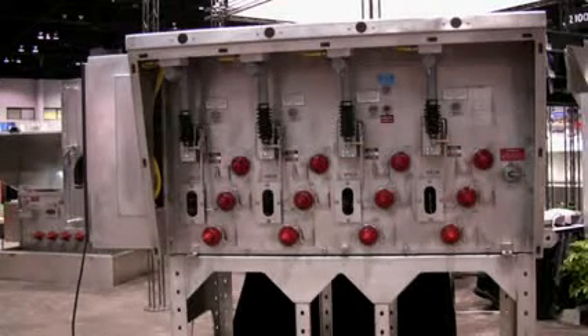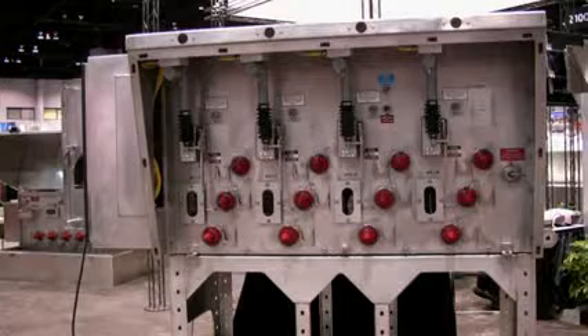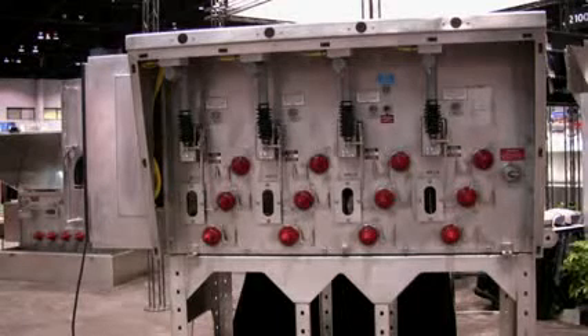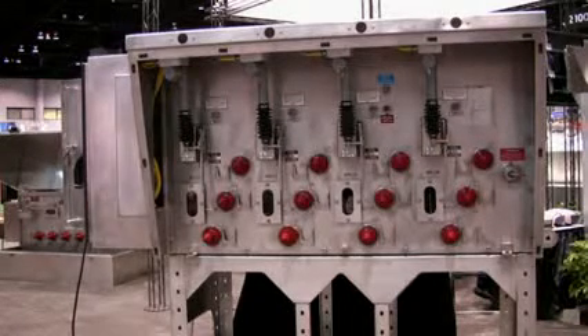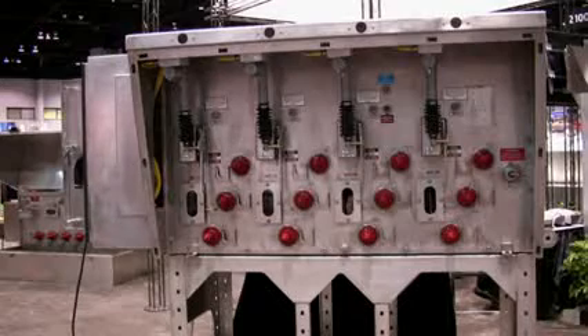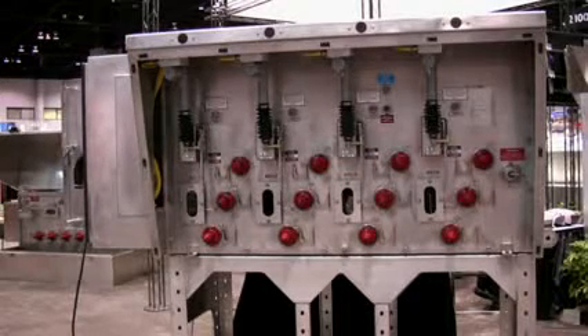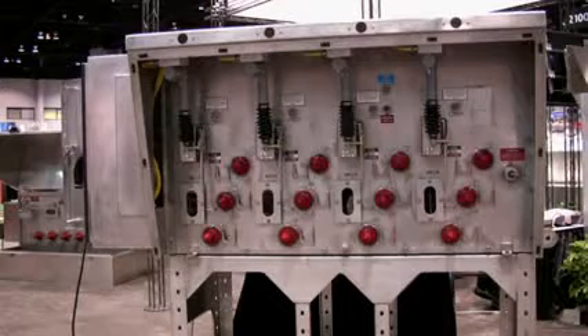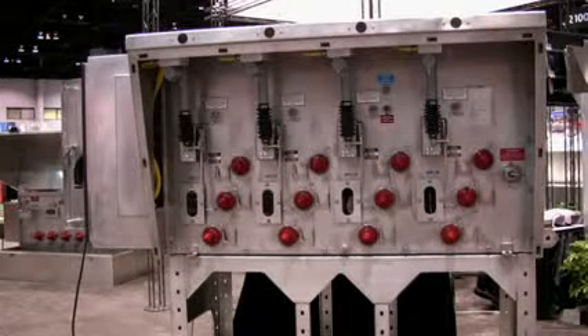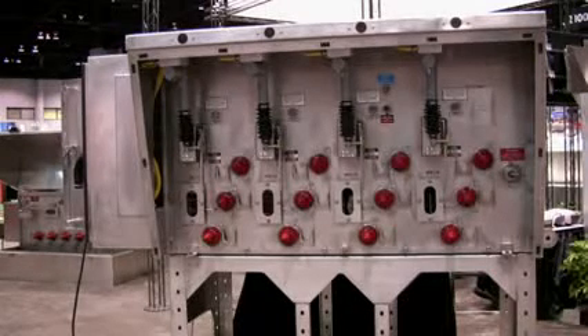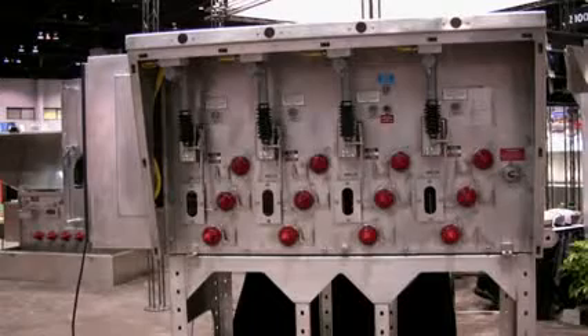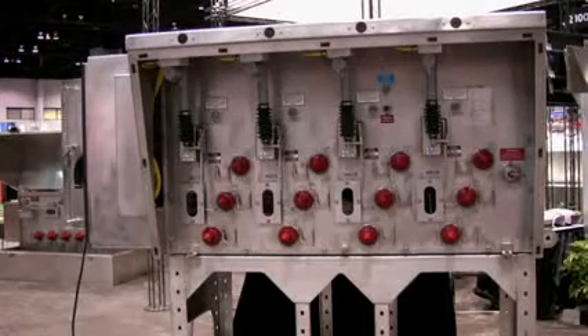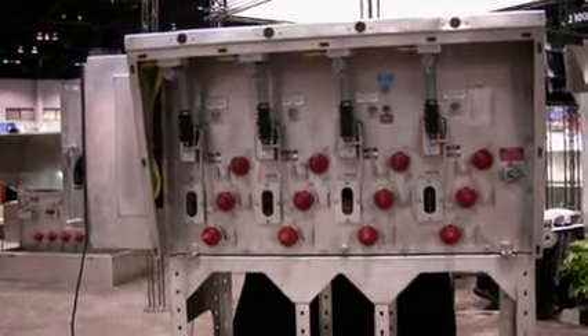You'll notice this unit already has windows in the top sill for the customer to put their fault indicators in. Everything is all pre-wired with control power. So all the customer has to do is bring in their high voltage cables, connect their high voltage cables, put their fault indicators in, and add their communications platform, which they happen to use a radio. Let's go and look at the control box now.